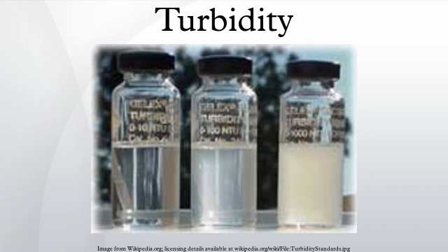Reagents. There are a number of chemical reagents that are available for treating turbidity. Reagents available for treating turbidity include aluminium sulfate or alum (Al2(SO4)3·xH2O), ferric chloride, gypsum, polyaluminium chloride, long-chain acrylamide-based polymers and numerous proprietary reagents. The water chemistry must be carefully considered when chemical dosing, as some reagents, such as alum, will alter the pH of the water. The dosing process must also be considered when using reagents, as the flocks may be broken apart by excessive mixing.